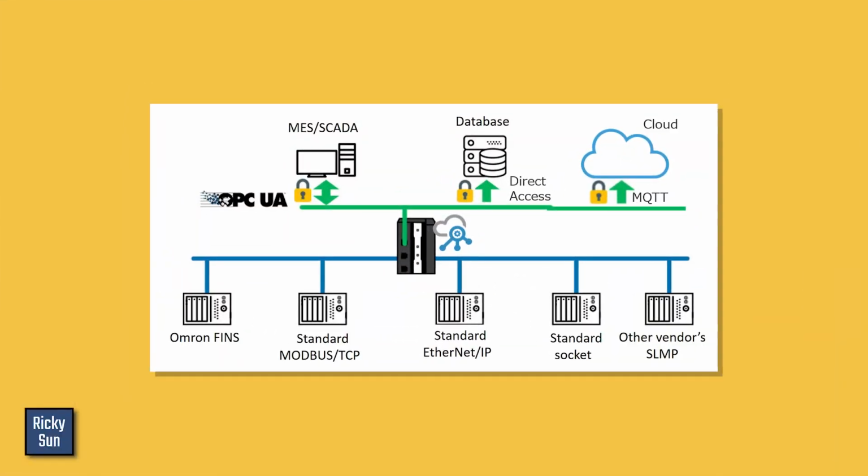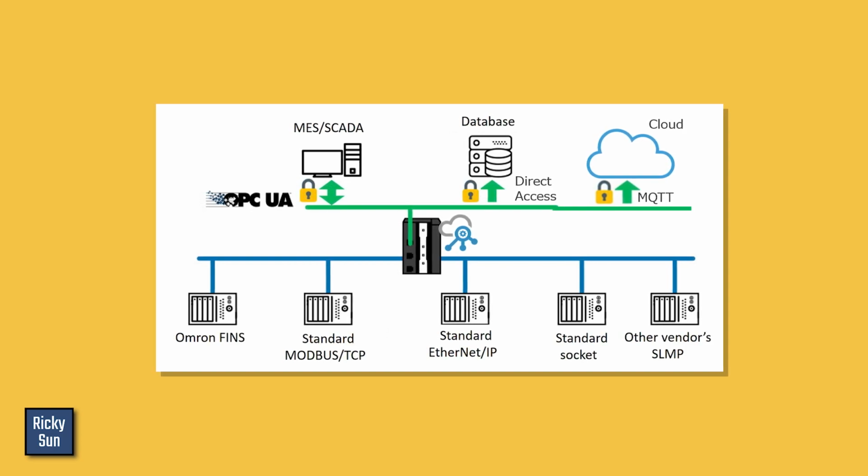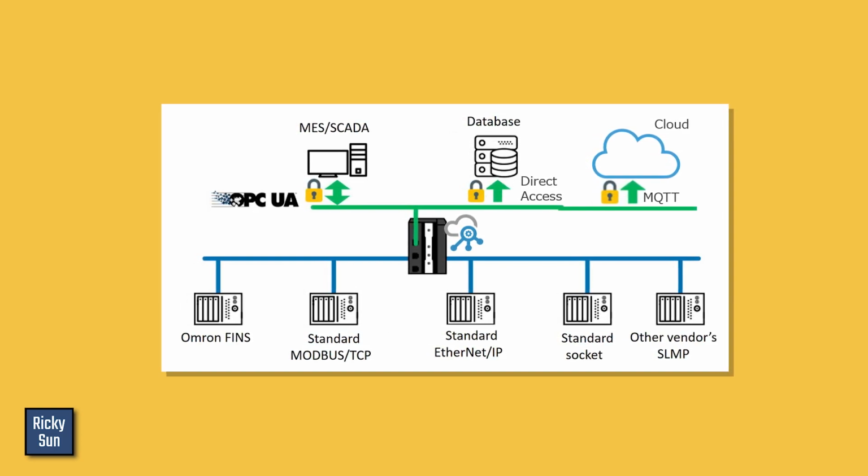I wish there were a Pi connector for HDA, but it doesn't have one. There is OPC UA. Most modern control systems, SCADA, will have OPC UA, and then you just use that connector. The connector would help you split the scan classes and the instances. You only need one instance, and it will take care of everything. That's what I wanted to share today about the OPC DA interface and the OPC HDA interface and their differences.